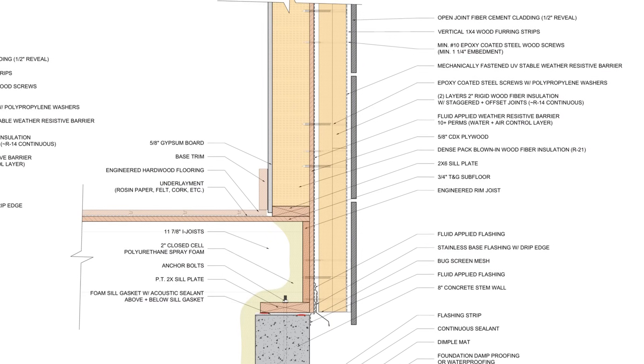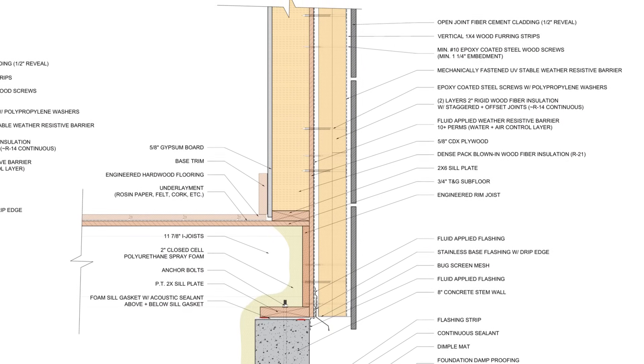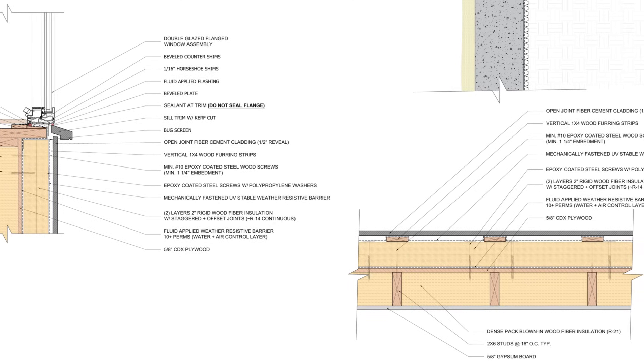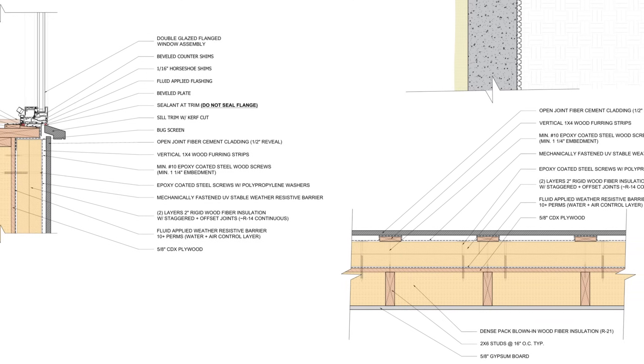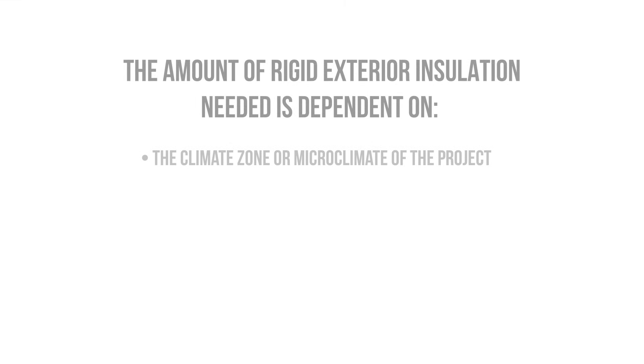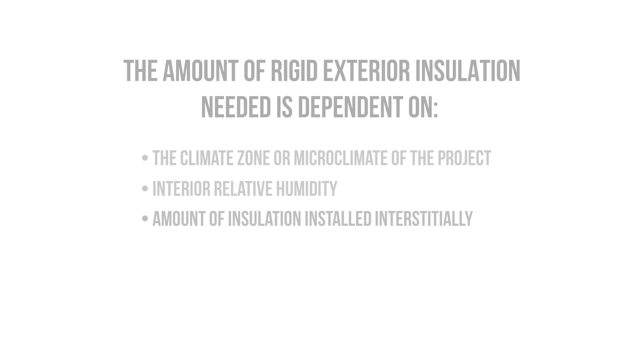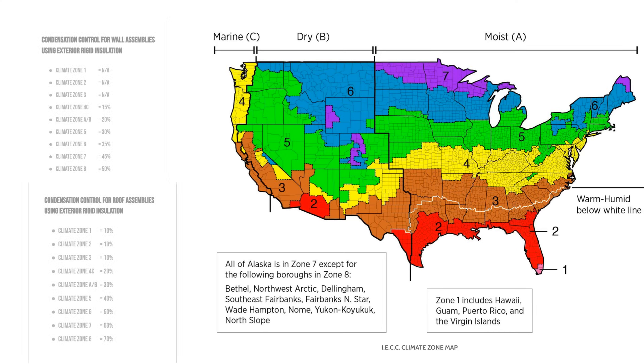At a minimum, we want to install enough rigid insulation outboard to prevent condensation on the backside of the sheathing. This amount will vary depending on the climate or microclimate that you're building in, the relative humidity that you're operating under, and the amount of insulation that's been installed interstitially. I'll put up the minimum recommended ratios from Building Science Corporation that were the basis for current building codes, but understand that more is better in this case.